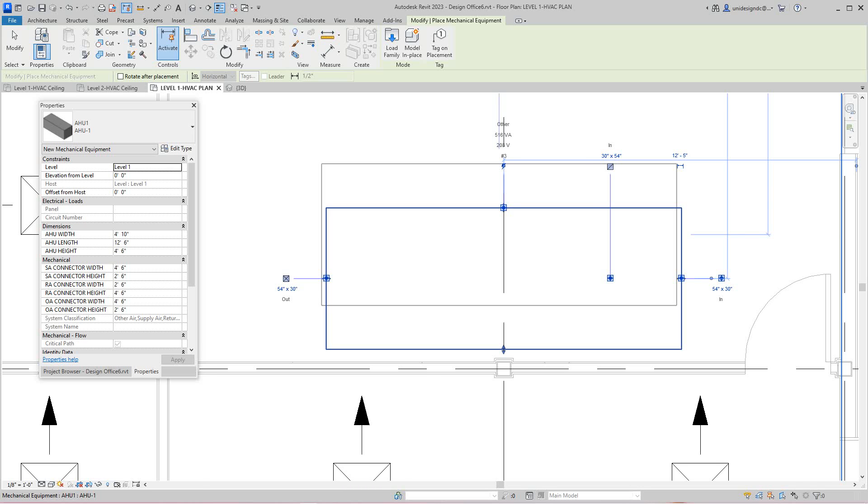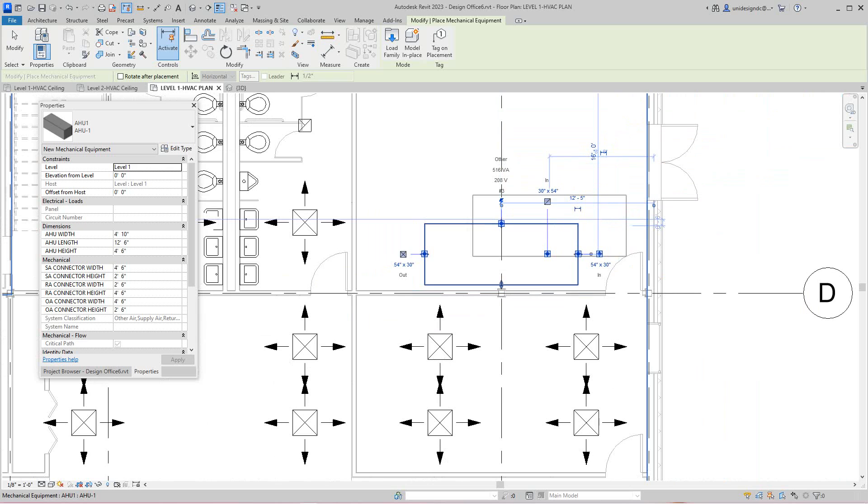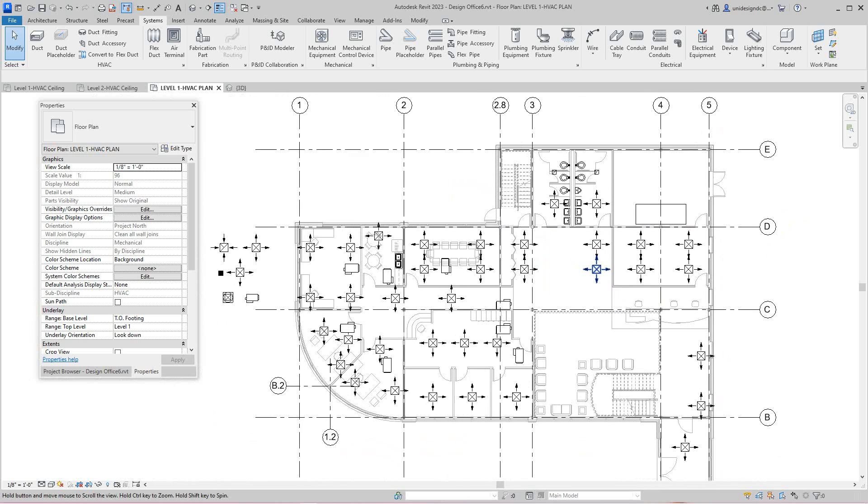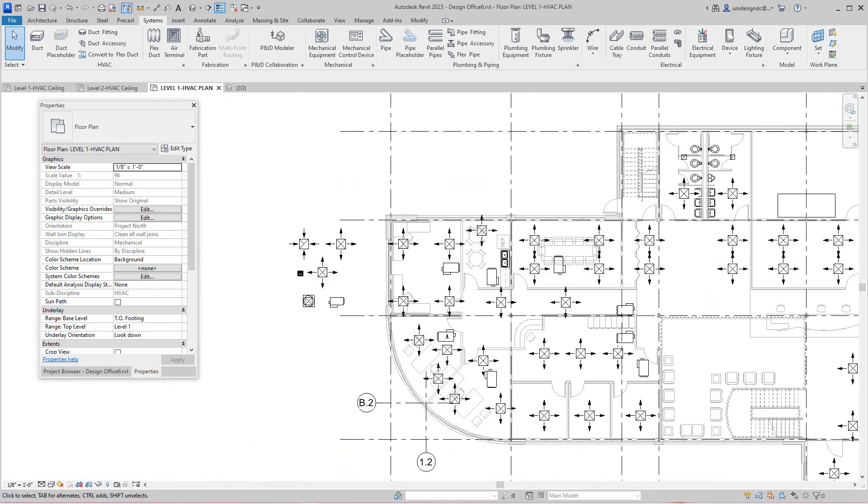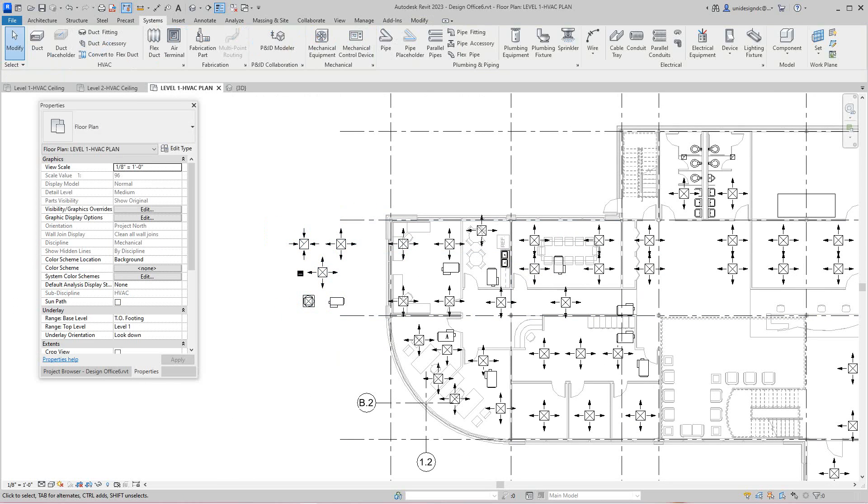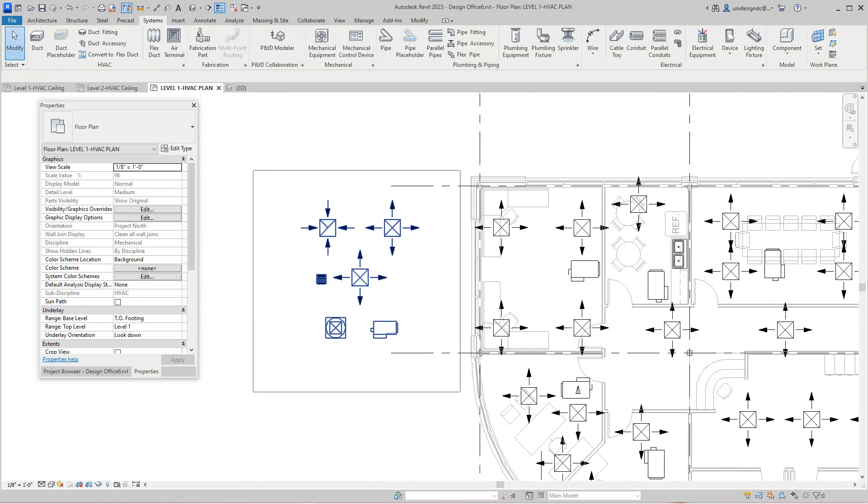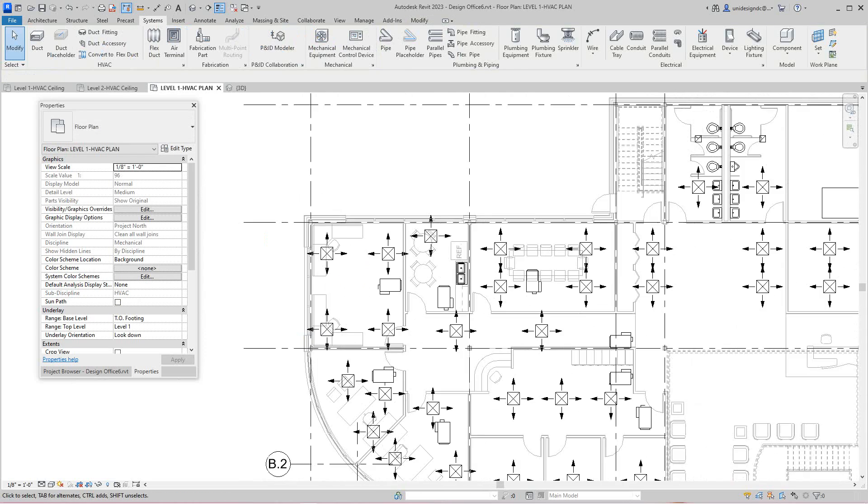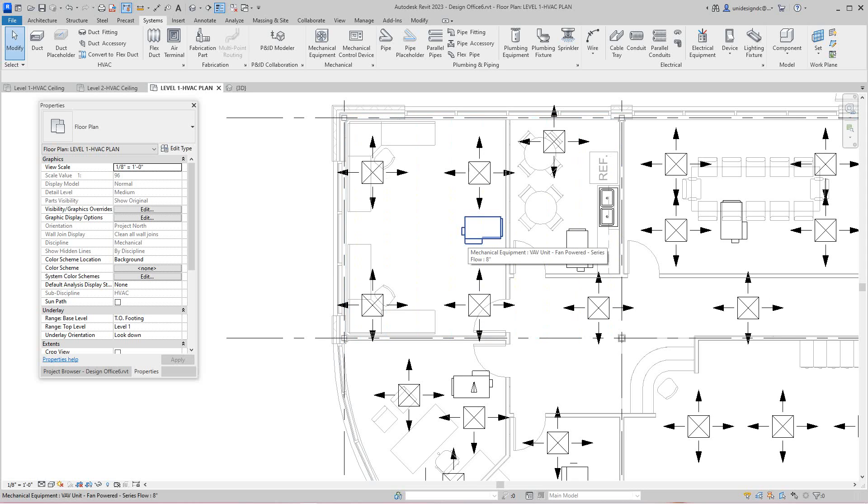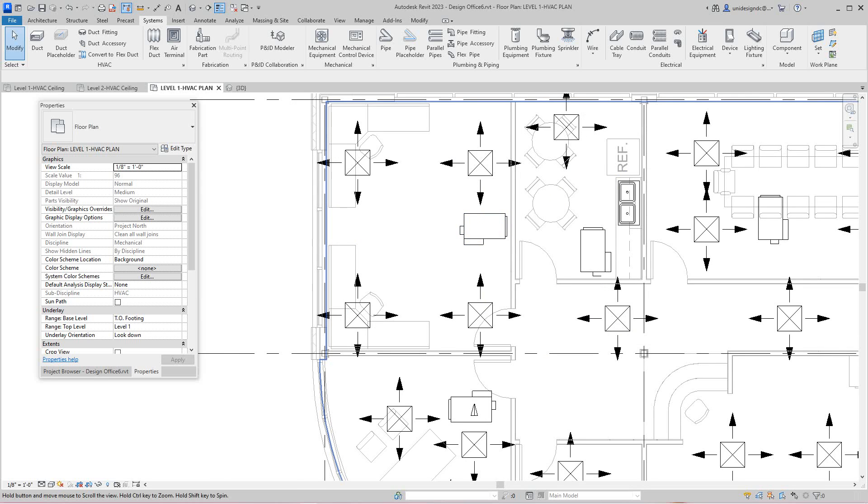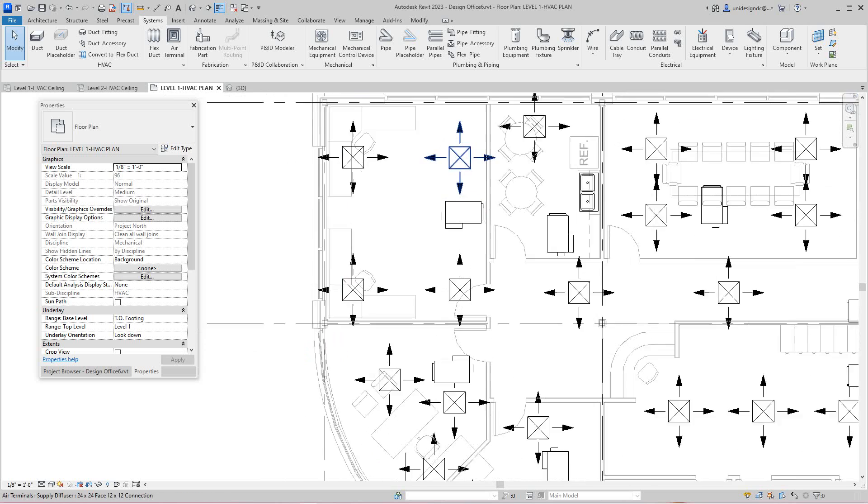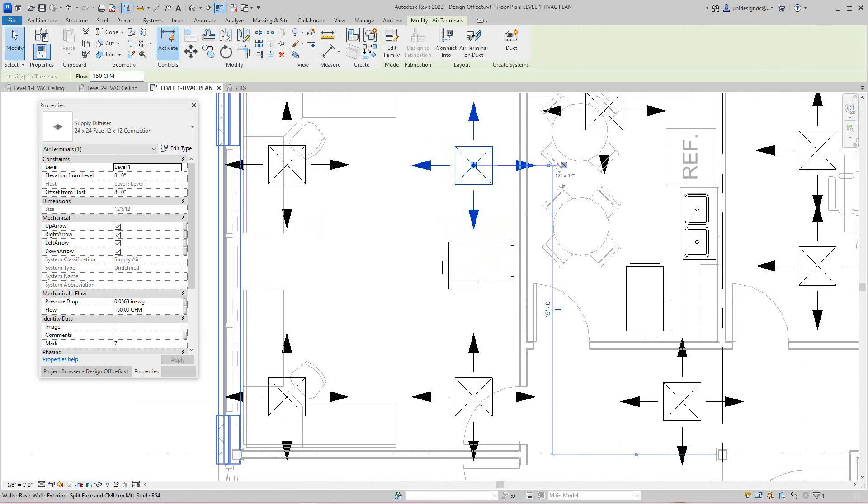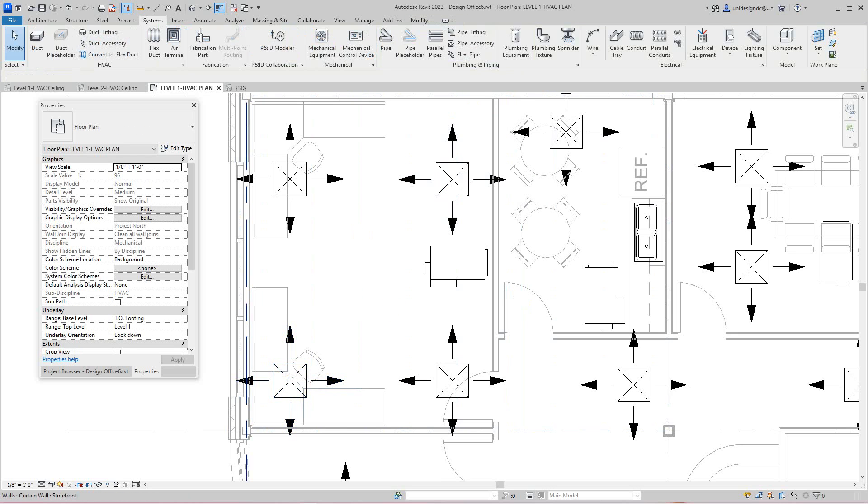Now here we have what you call a VAV box, a variable air box. It variates airflow into the rooms. Now if I look here and select these diffusers, I've got them set at 150 CFM and they're all at that level. That's based on the need in the rooms here. These are lower, so you're going to have to go and change all those if you follow along or use what they're using in the book.